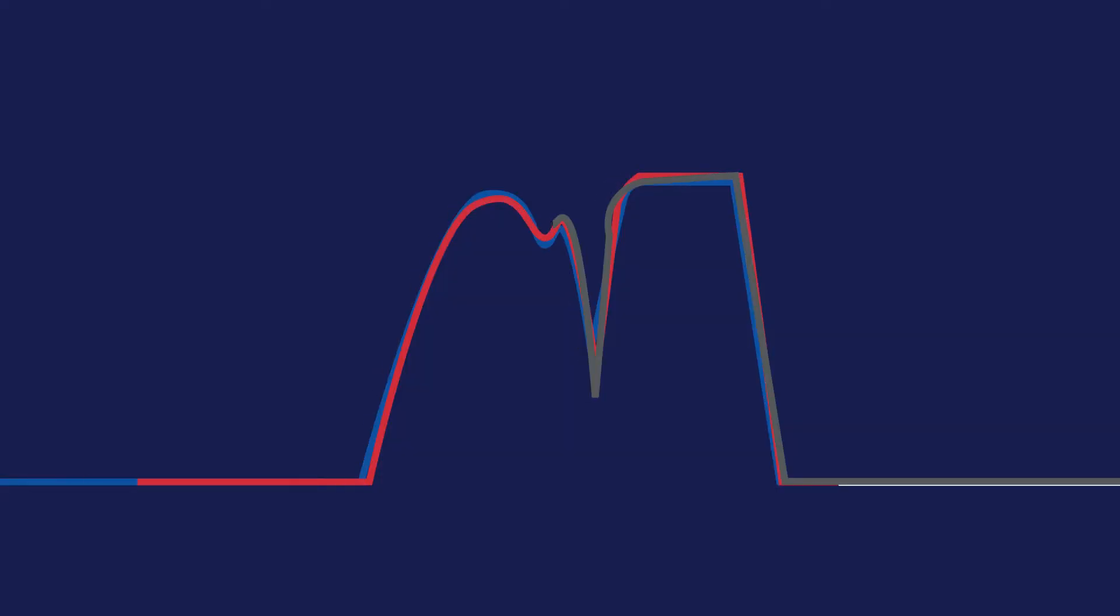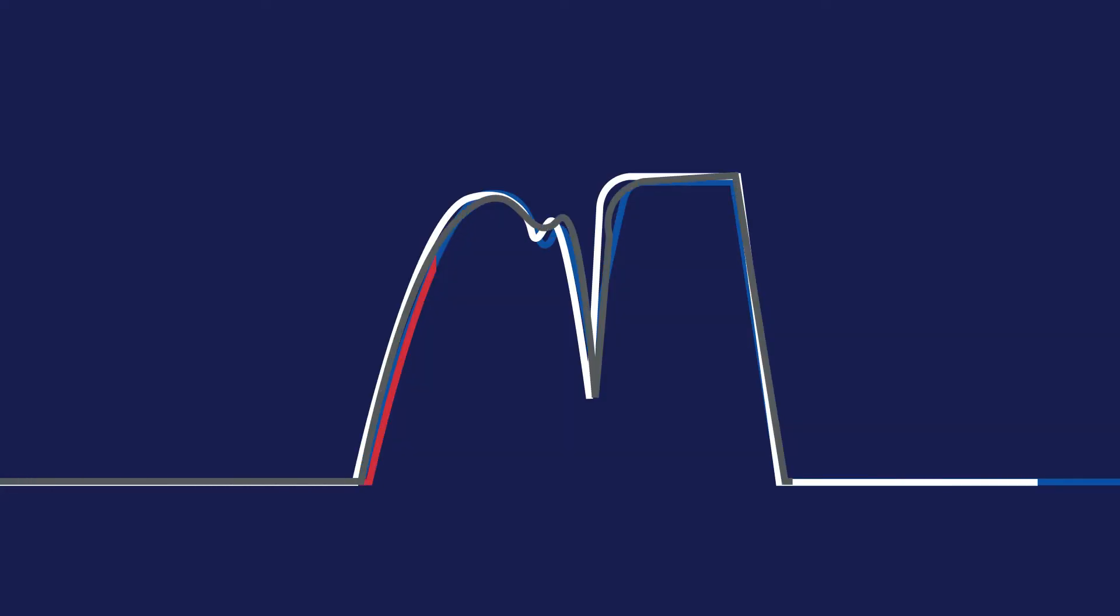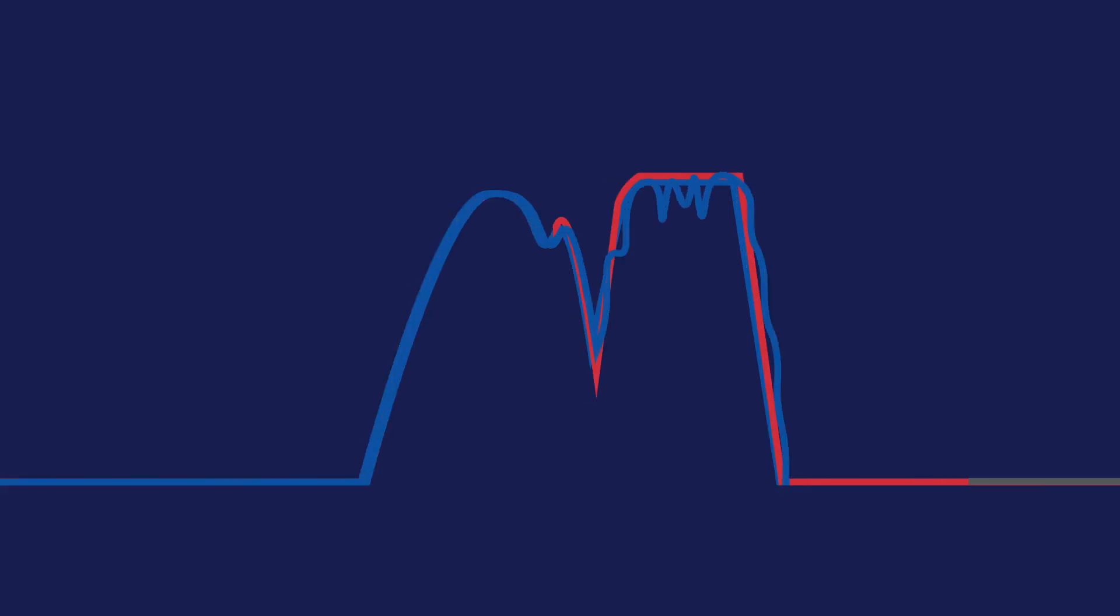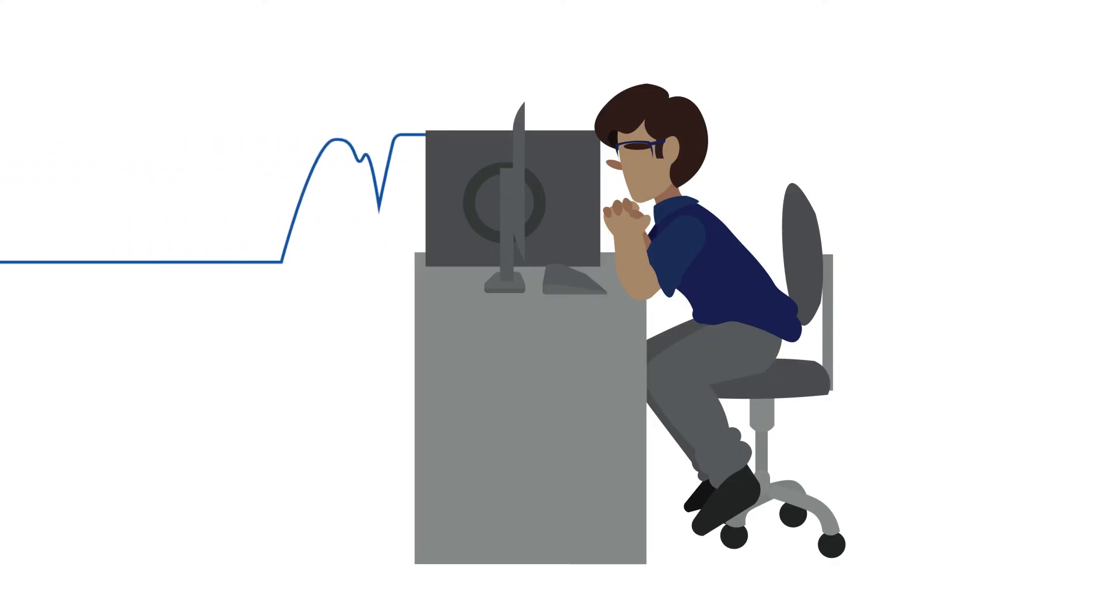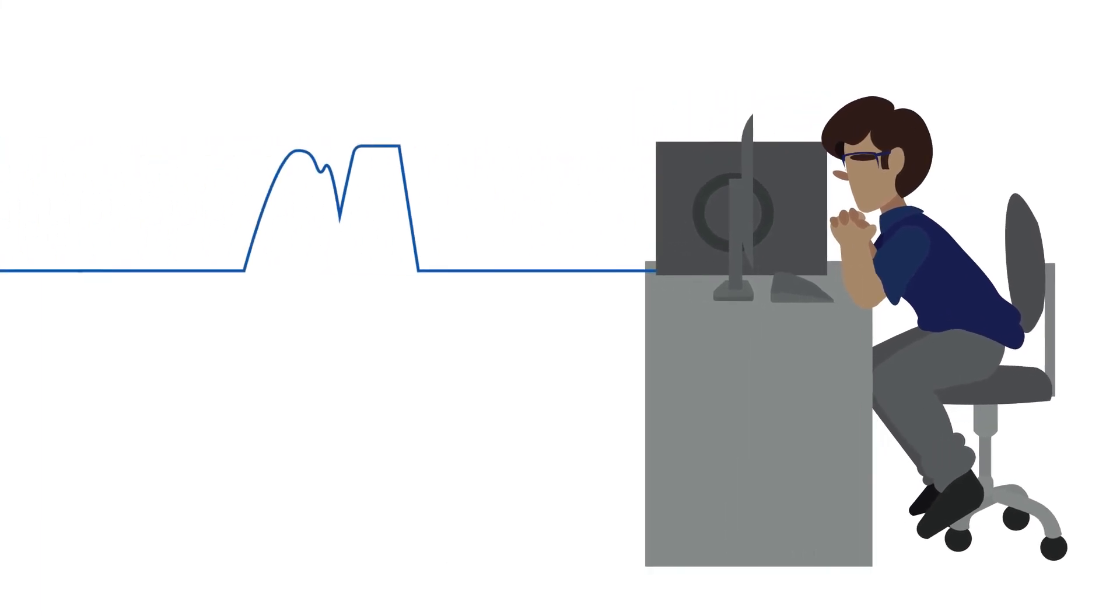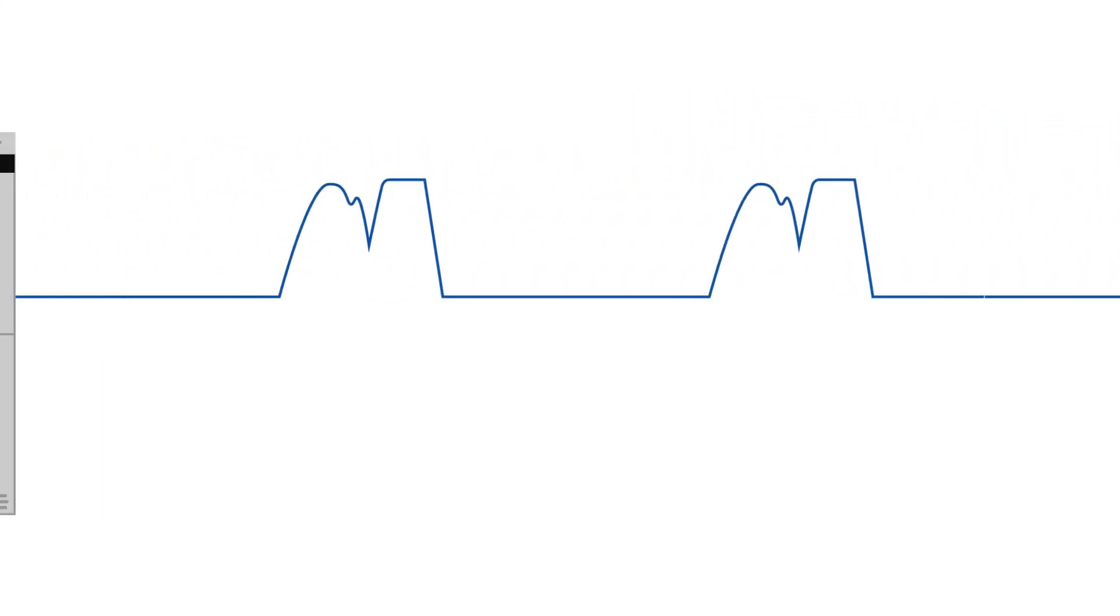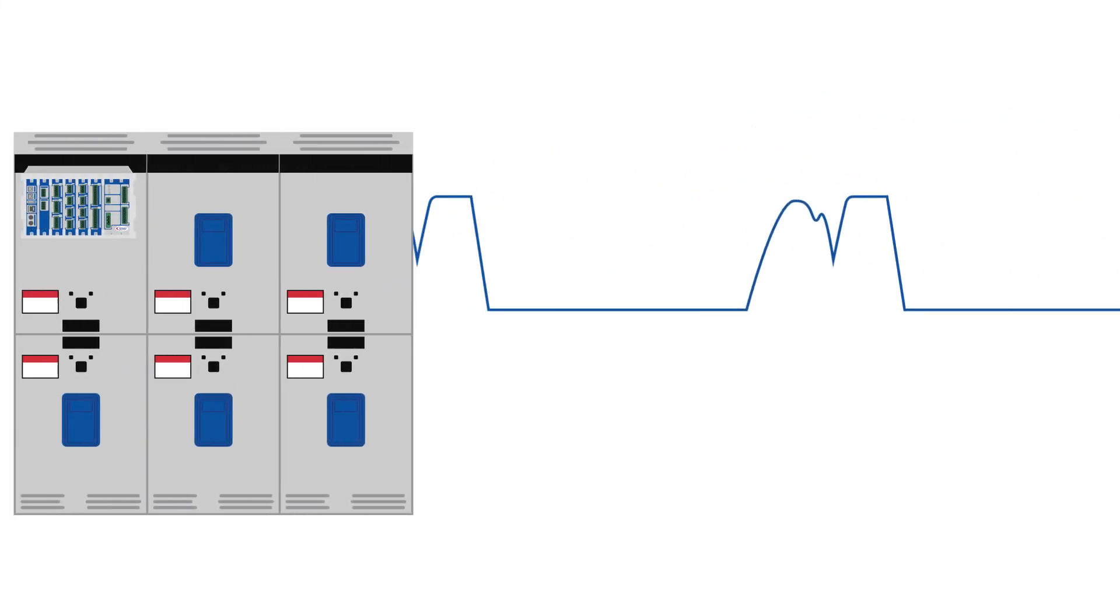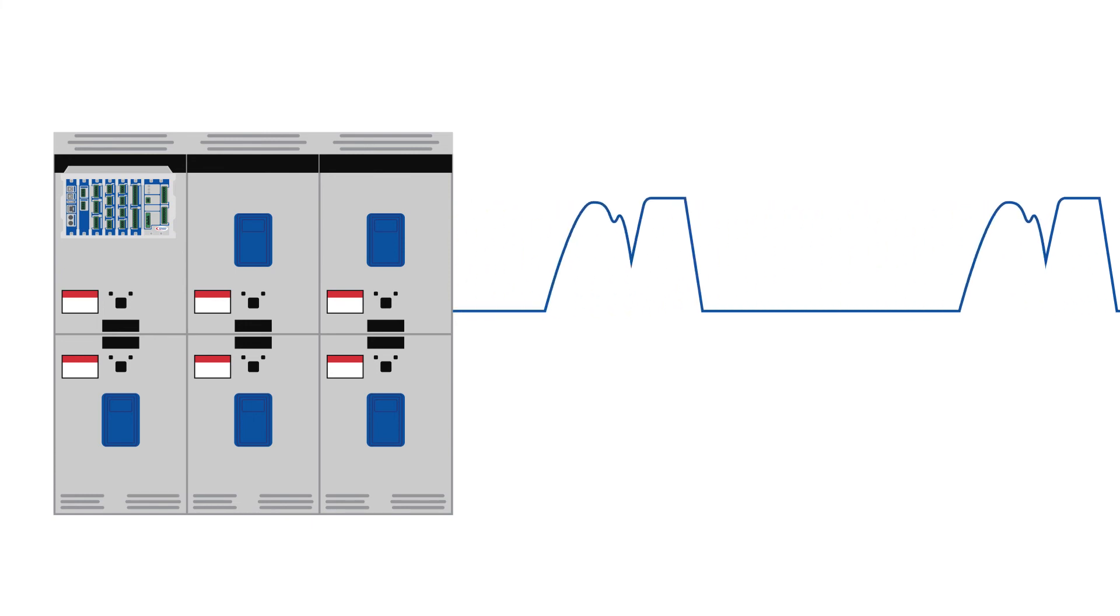Variations in the waveform capture are easily associated with the mechanical performance of the switchgear's various parts, allowing many operational deficiencies to be detected in their earliest stages and providing detailed data concerning the diagnosis of these problems.